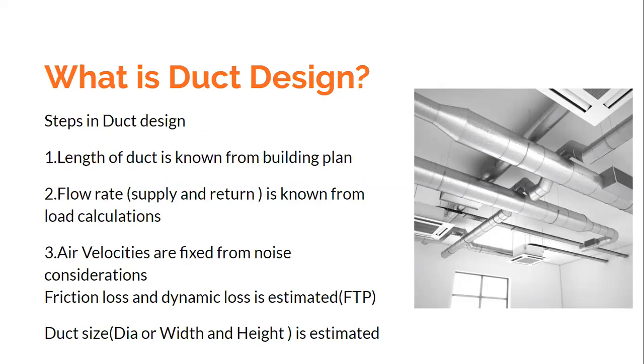What exactly do you do during duct design? What are the steps? First, you need to contact the architect and ask for the building plan. That building plan gives you the location of the spaces you need to condition, which helps you locate the Air Handling Unit (AHU). Once the AHU location is known, you can estimate the length of the duct from the AHU up to the space to be conditioned — that is the supply duct.